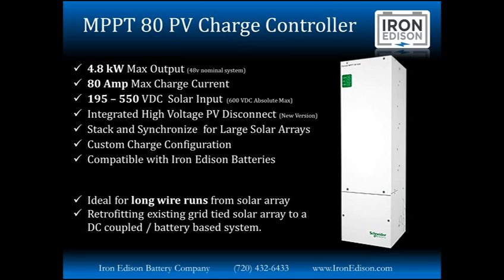This is a high voltage charge controller. It'll put up to 80 amps max charge current into the battery. But the unique thing about this charge controller is it'll accept between 195 and 550 volts DC from the solar array. It also has an integrated high voltage PV disconnect built into it, because you probably know you can't get high voltage circuit breakers very easily anyway when working with high voltage systems. Again, you can stack and synchronize these inverters or charge controllers for large solar arrays, and it also has the custom charge configurations that Brandon mentioned, making them perfectly compatible with Iron Edison batteries.